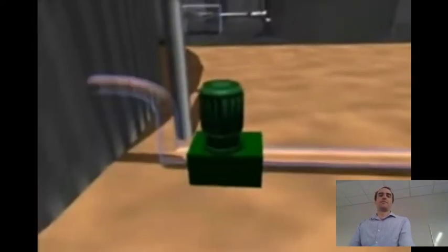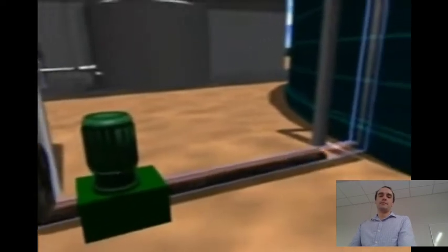The substrates are continuously stirred in order to prevent layers of material forming at the top or on the bottom. A hot water wall heater heats the substrate to between 35 and 55 degrees centigrade in order to accelerate the formation of methane. On average, the substrate is in the fermenter for a period of around 30 days, before it is filled into another fermenter for a further 30 days to complete the gas formation process.